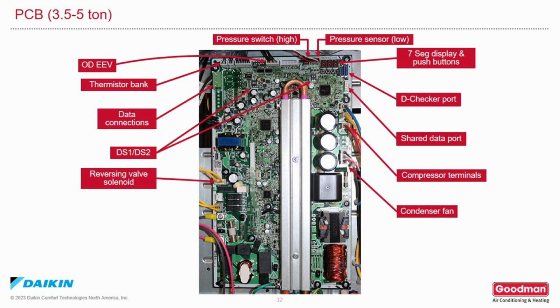Here is an example of a 3.5 to 5 ton circuit board. You'll see that the connections are all present on this board as well. However, the main difference is there is no heat sink on the back side of the board. Instead, you'll see a DX loop run across the board and attached to the inverter circuit.